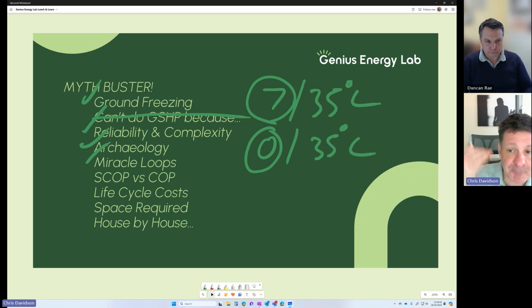So if you're comparing air source and ground source or other types of system with COP only, you're not doing justice to the technologies. You've got to look at seasonal COP, which is the annual heat delivered divided by the annual electrical consumption. Now, from a ground source point of view, that's pretty easy to work out, because in the design software, if you give us hourly loads, we can give you that COP by the hour and therefore give you a very accurate seasonal COP.